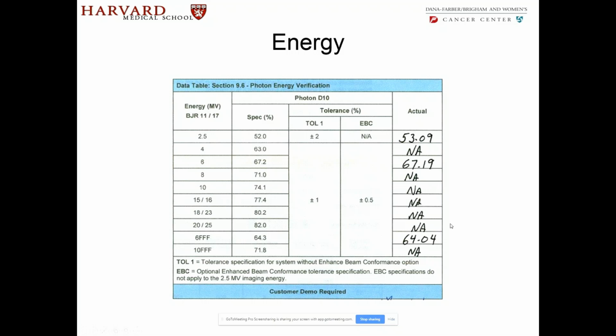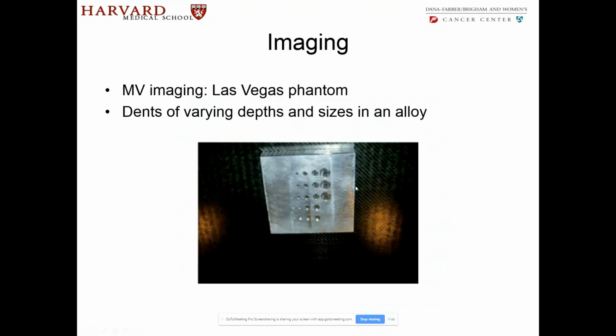Okay. When it comes to imaging, they have this phantom called the Las Vegas phantom for MV imaging. It's an alloy which has different amounts. They have dents of different depths and sizes. They're all circular.